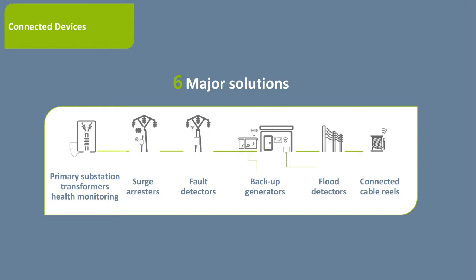We gained new features with backup generators, such as GPS position. Imagine knowing the exact location of a backup generator. In crisis management, with hundreds of backup generators in the field, knowing precisely where they are helps coordinate efforts. We also get a good feel for operating status, knowing if they're running or not in live conditions. We're notified with alerts of the need to refuel, because it's a pity when a backup generator runs out of fuel and stops generating power. We can better coordinate crisis management efforts thanks to this. It's a real game changer.